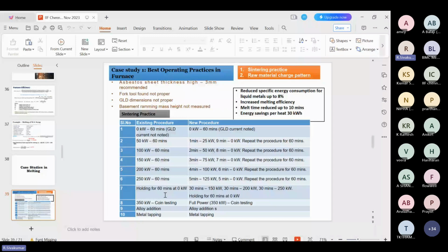In earlier practices, for 0 to 60 minutes, the GLD current was noted. So 0 kilowatt for 60 minutes, GLD current noted as it is. The second step is 50 kilowatt given for 60 minutes. Here we give 1 minute of 25 kilowatt and 9 minutes of 0 kilowatt. That means every 10 minutes, one cycle is there. For 1 minute, the 25 kilowatt is given, 9 minutes power is off. So repeatedly it is done for 60 minutes, that is 6 cycles.